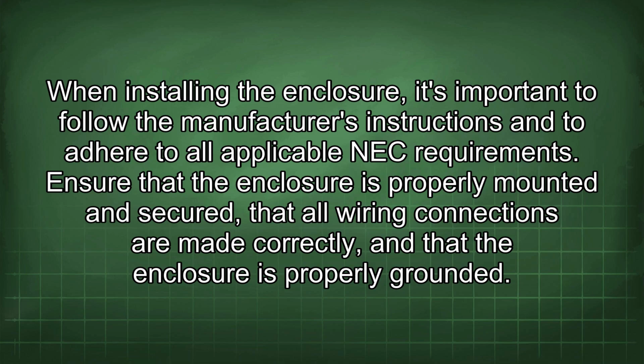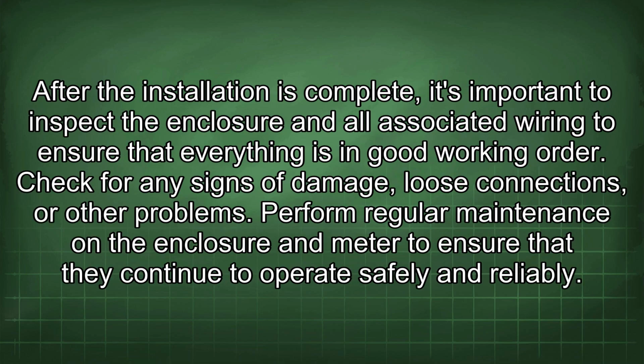When installing the enclosure, it's important to follow the manufacturer's instructions and to adhere to all applicable NEC requirements. Ensure that the enclosure is properly mounted and secured, that all wiring connections are made correctly, and that the enclosure is properly grounded. After the installation is complete, it's important to inspect the enclosure and all associated wiring to ensure that everything is in good working order. Check for any signs of damage, loose connections, or other problems. Perform regular maintenance on the enclosure and meter to ensure that they continue to operate safely and reliably.